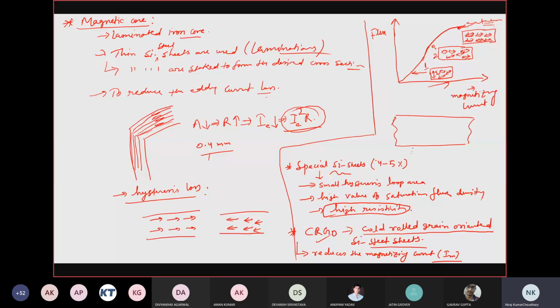तो जो प्रॉपर्टी सपोज यहाँ सेकंड कंडीशन में आ रहा है. So how was this property achieved? When we have excited the magnetic material through an external source, that is when you are applying the exciting current through the coil wound on the magnet, electromagnet. But here in case of CRGO sheets, without any external excitation, due to the cold rolling of the laminated sheets, the grains are automatically oriented to some extent in the direction of magnetization.